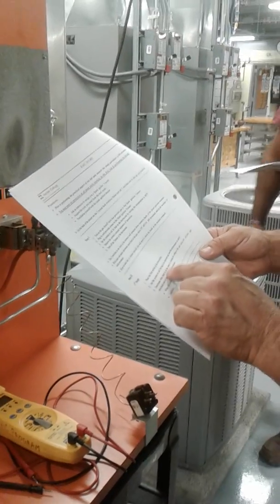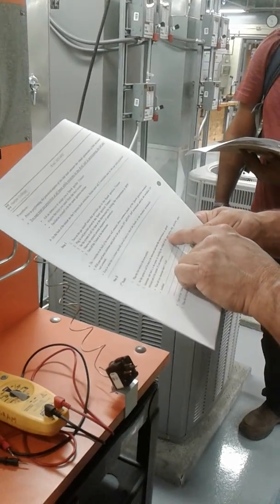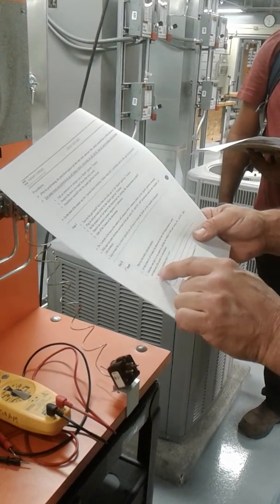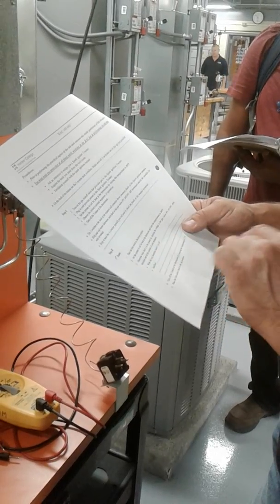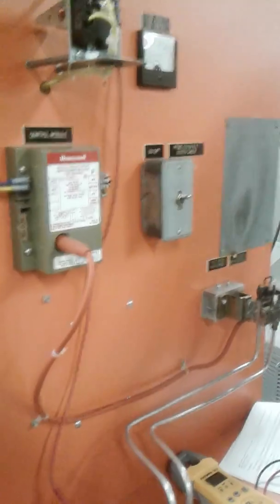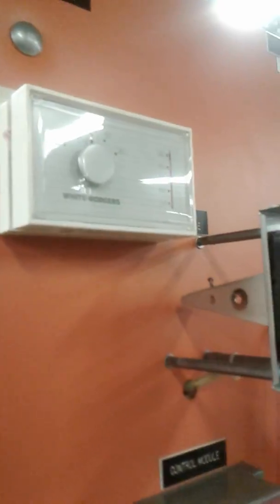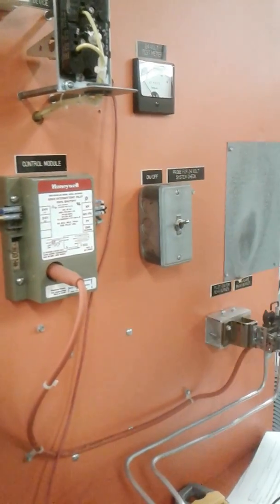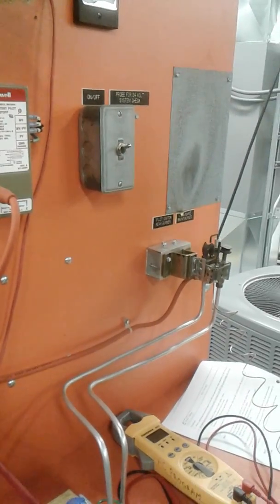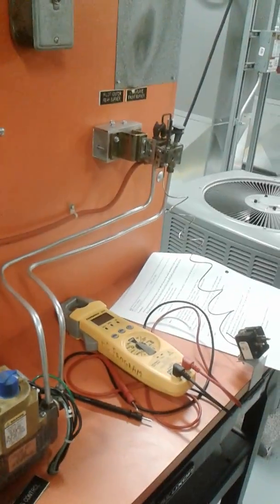Now, it says here, place the first switch in the down position. So I'm going to take switch number 1 and put it in the down position because the paper told me to. Set the system to call for heat at the thermostat. Determine what fault is in the system by checking the voltage at the gas valve, PV, MV terminals, and the module 24 volts. What did you determine to be fault number 1, and then justify your answer? Switch 1 is in the down position, so let's call for heat. Nothing. Nothing. Check it out.